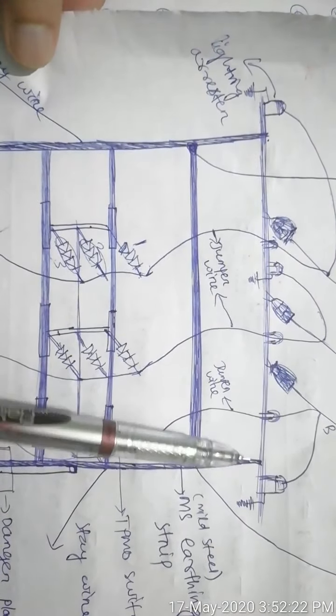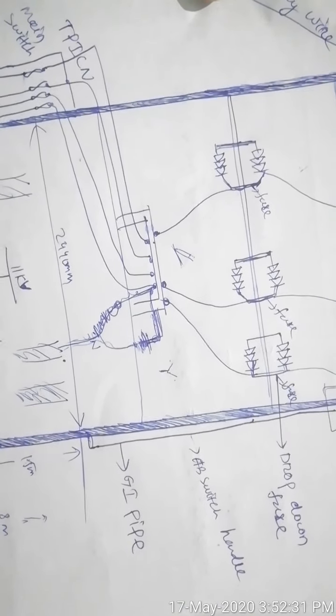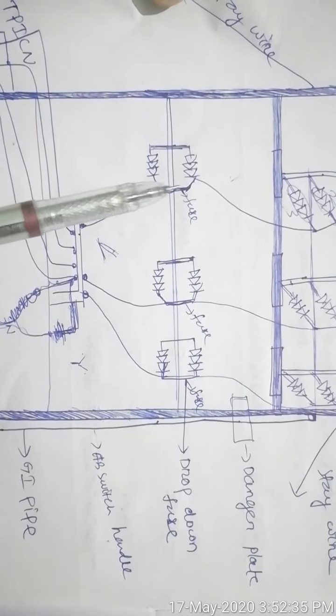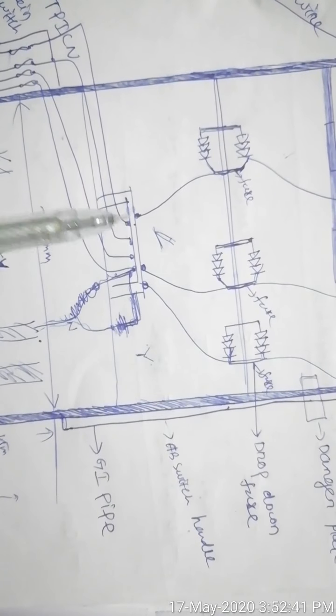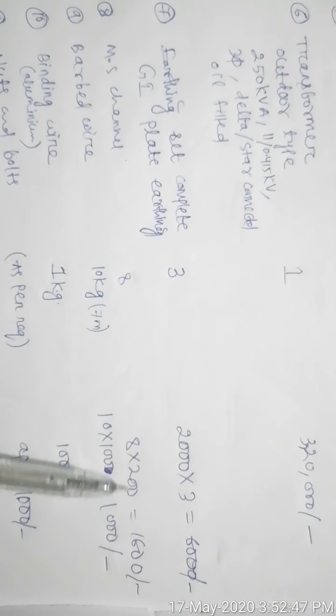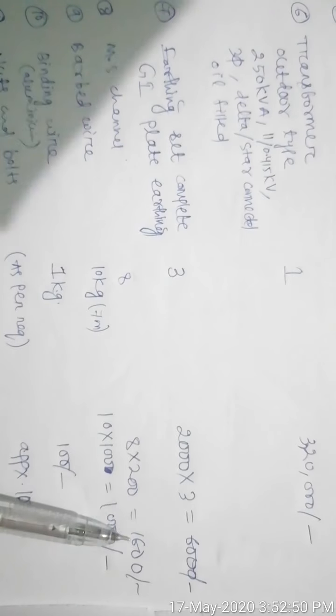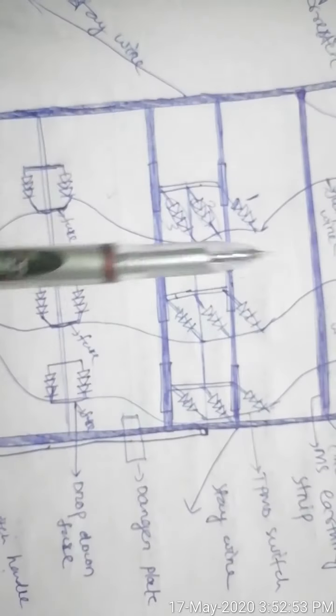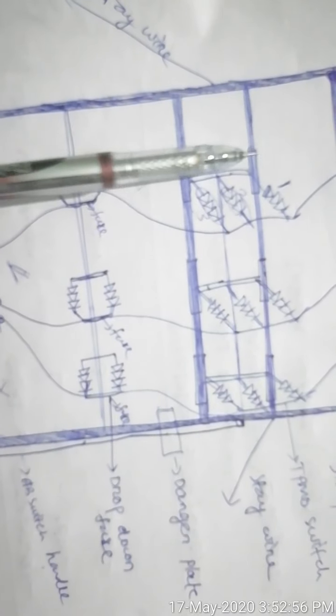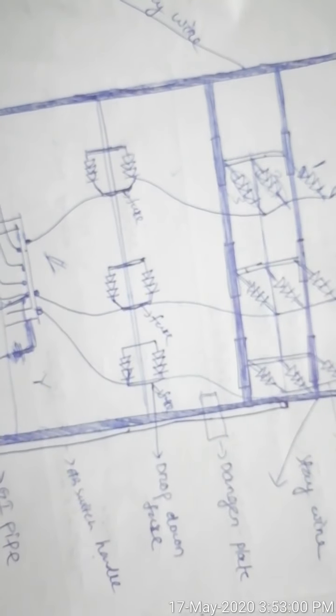MS channels are those mild steel rods which are connected between these two poles. These are called channels, and a total of 8 channels are required to design the pole structure so that the individual components can be placed on it, like the TPMO switches, fuse units, and transformer need to be placed on these channels. Individual channel costs 200, so a total of 1,600 needs to be invested in it. If we count the number of channels, 1 2 3 4 5 6 7 8.